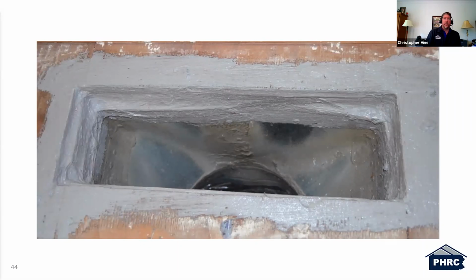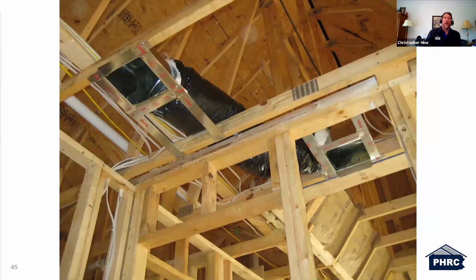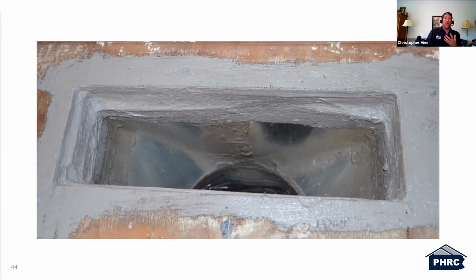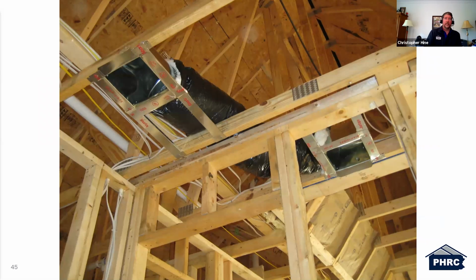So here's a picture of a boot coming through the subfloor with mastic. Beautiful installation, right? I'm sure this is what we're all seeing. But that's pressurized. That is a supply run. A lot of care is taken into making sure that that's sealed.